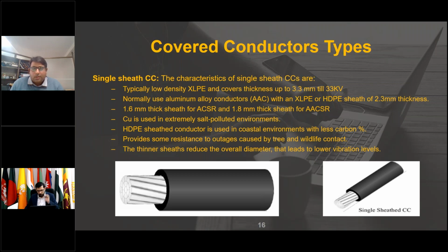The characteristics of these single sheath covered conductors are that they are typically of low-density XLPE with cover thickness up to 3.3 millimeter up to 33 kV. Just to add to this, the insulation has a direct link with the voltage. As you increase the voltage level, the insulation gets thicker and thicker. So normally aluminum alloy conductor with XLPE or HDPE sheets of 2.3 millimeter thickness can also be used. So 1.6 millimeter thick sheet for ACSR and 1.8 millimeter thick sheet for AACSR. These are basically the classifications of the thickness of the insulation attributed to those conductors when they are in covered conductor arrangement, single sheath.